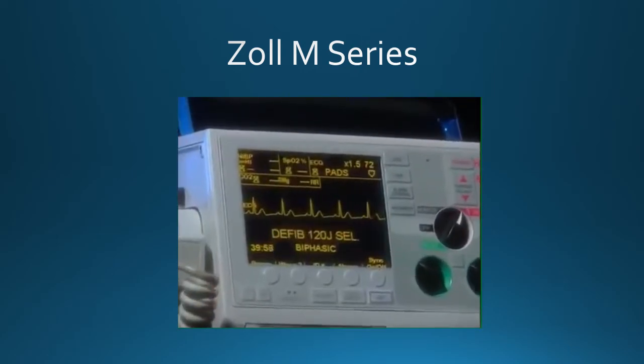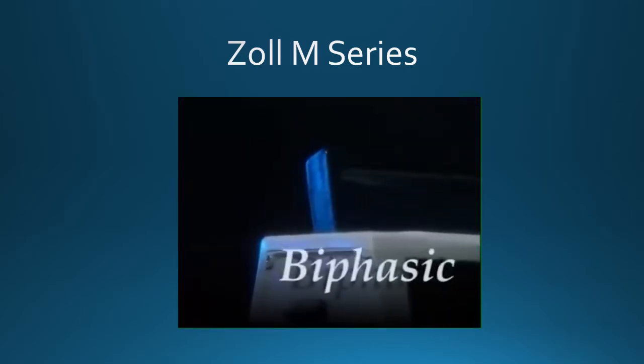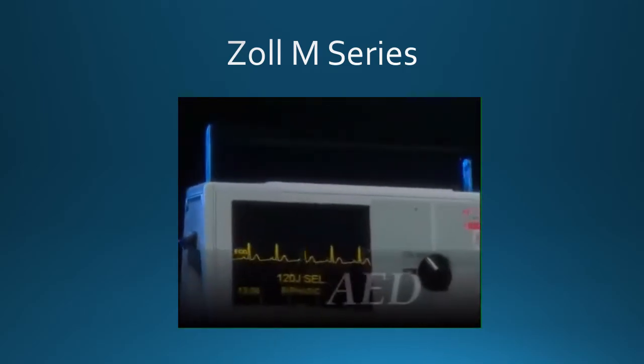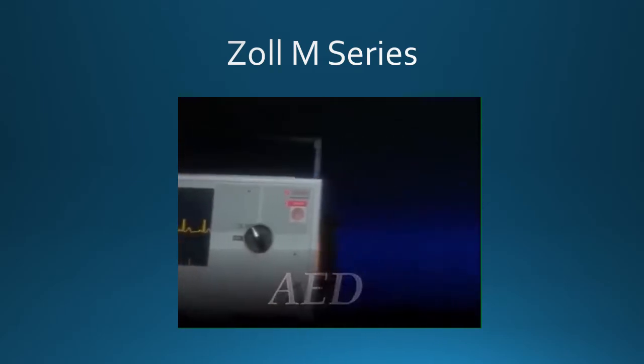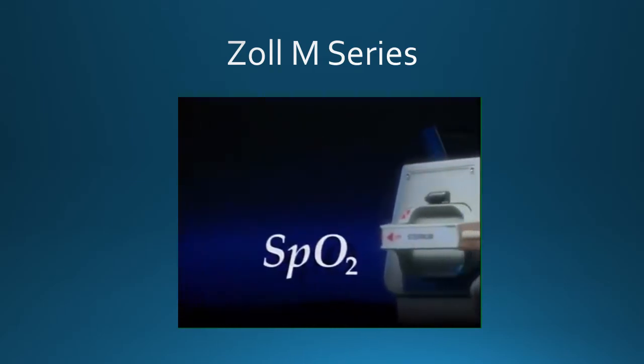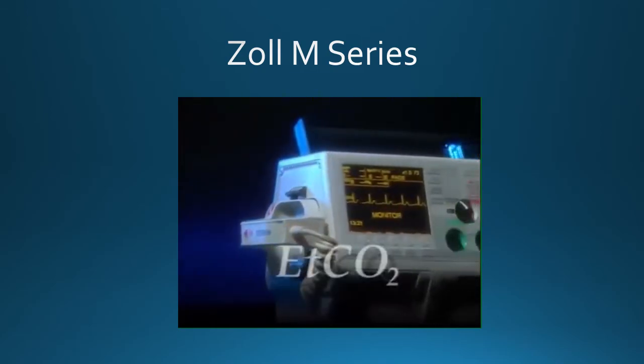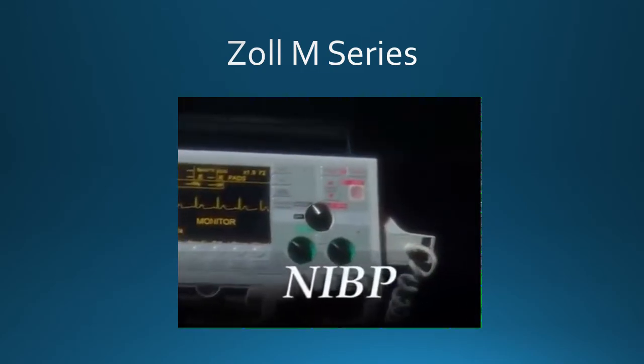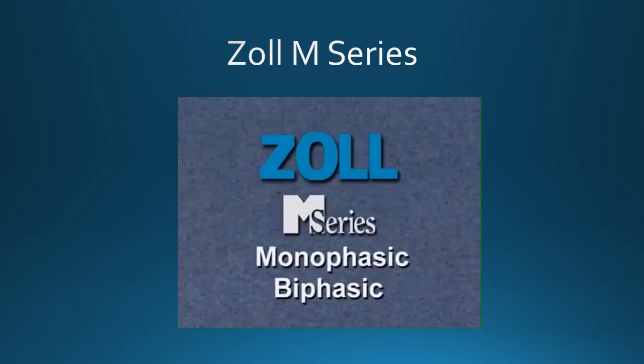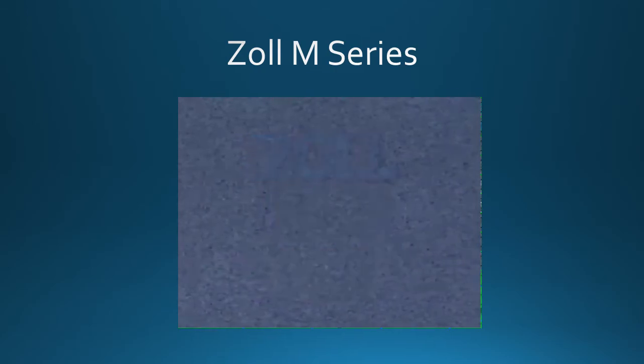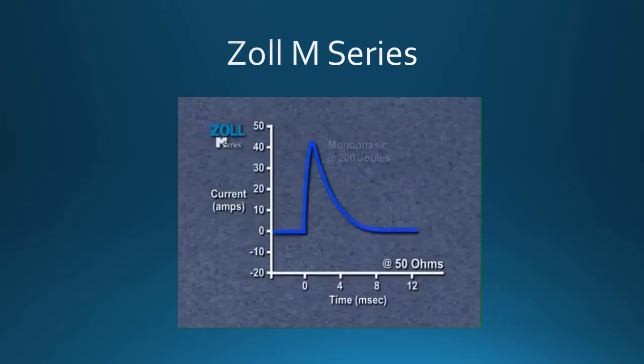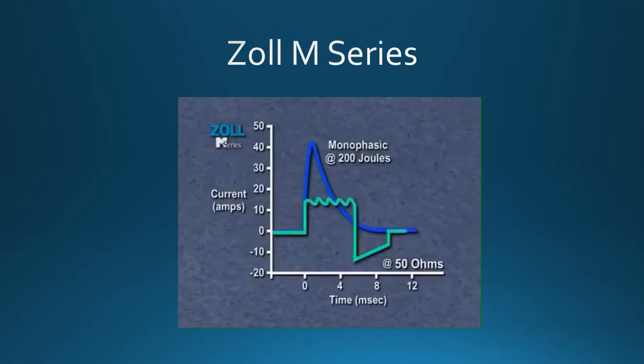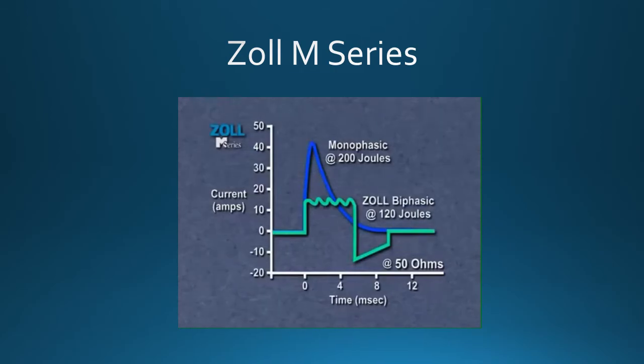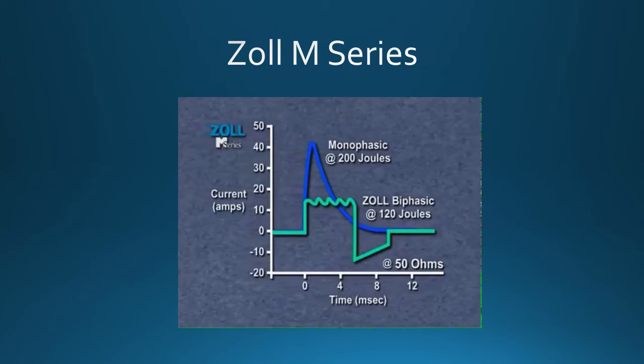This second program will introduce you to the Zoll M-Series with Zoll's low-energy rectilinear biphasic waveform, AED function, and additional monitoring parameters including pulse oximetry, 12-lead ECG, end-tidal carbon dioxide monitoring, and non-invasive blood pressure. M-Series are now available with a choice of 2 defibrillation waveforms. Some M-Series are equipped with a monophasic waveform, and some offer Zoll's new low-energy rectilinear biphasic waveform. The rectilinear biphasic waveform offers superior defibrillation capabilities at lower energy settings.